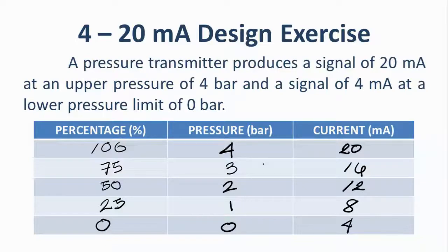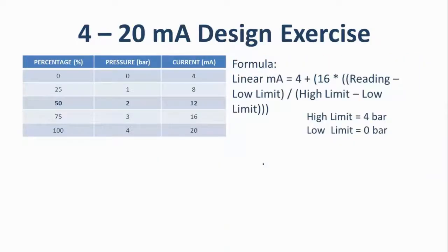There is a more efficient and accurate way to do this using a formula. For a linear response, the formula is: mA = 4 + 16 × (reading − low limit) / (high limit − low limit). In our case, the high limit is 4 bar and the low limit is 0 bar.